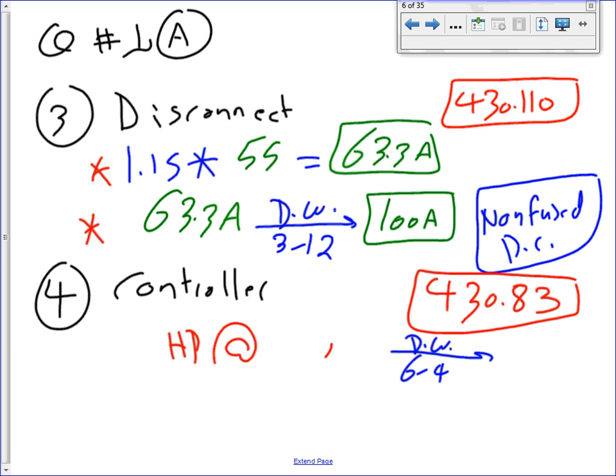Since you guys don't have disconnects, can you write yourself a note for the sizes that you guys are going to have? The sizes of disconnects are 30, 60, 100. Can you write yourself a note? You really don't have to, for a dwelling, go higher than that. So if you're 30 or less, you're 30. If you're between 30 and 60, you're 60. If you're between 60 and 100, you are 100. That's all. Most dwellings fall between these three sizes. After that, it becomes, for the most part, multiples of 100.